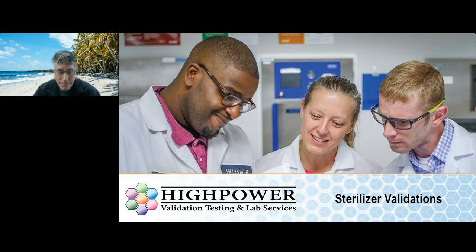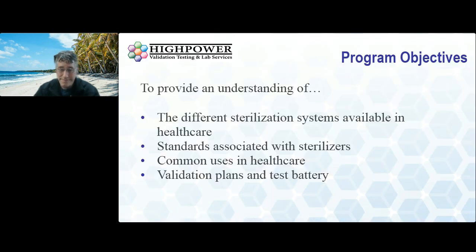High Power Validation Labs is a contract testing laboratory. We've been validating medical devices for well over 30 years. What a lot of people don't know about us is we validated sterilizers — that was a big part of what we've done. Our number one study ever in the late 80s was a sterilizer, and then the medical devices followed. We have about 40 people here in Rochester, New York. The most important thing I want to point out today is that sterilizers are medical devices if they are marketed to a healthcare facility, and they are subject to FDA approval as a Class II medical device.